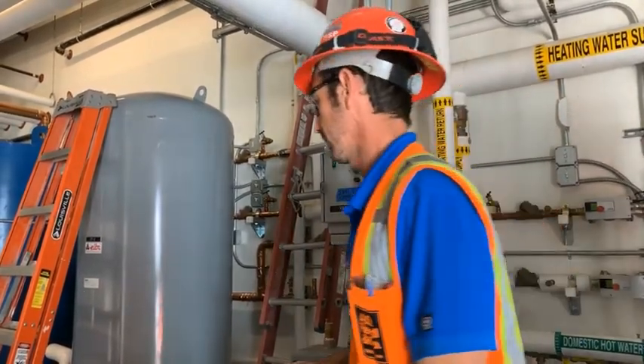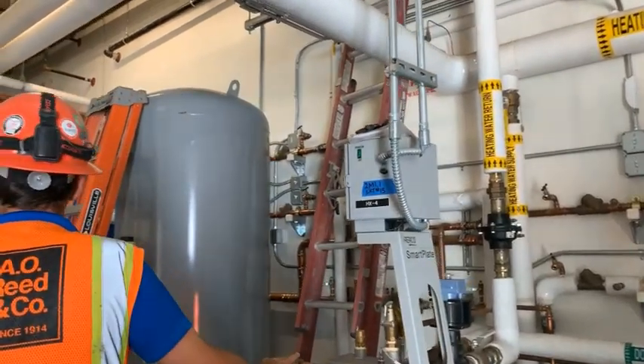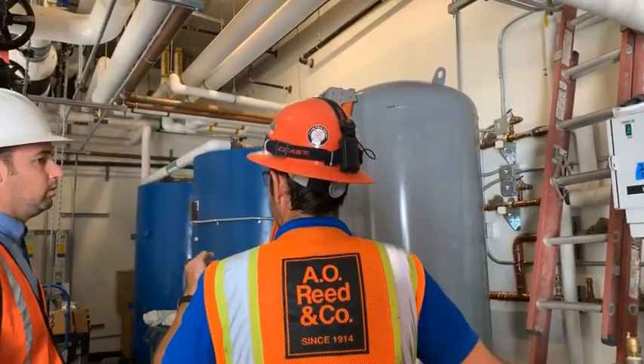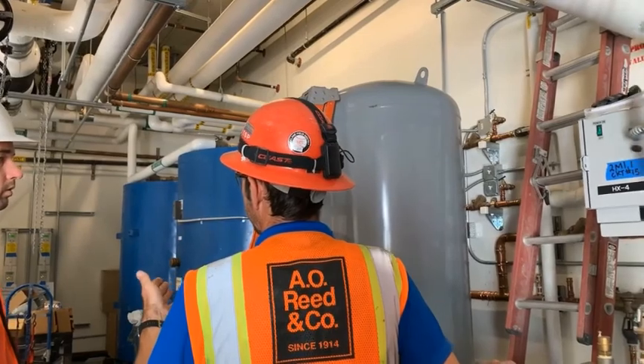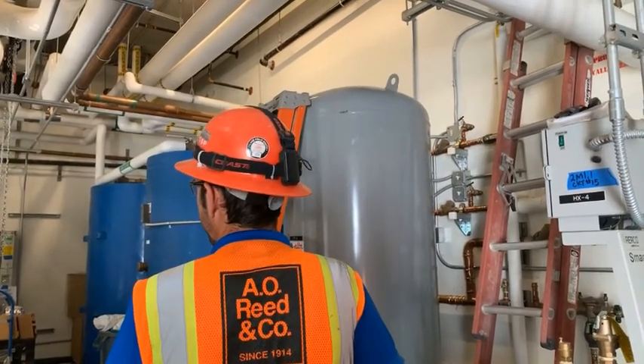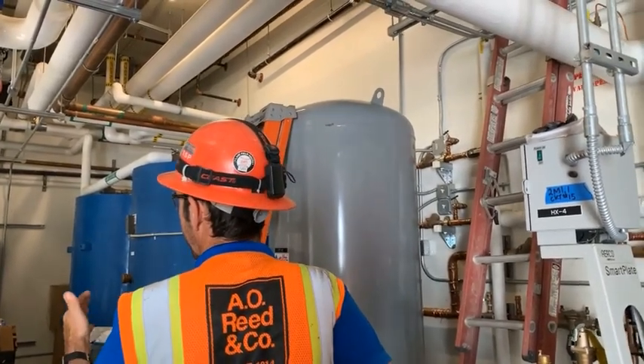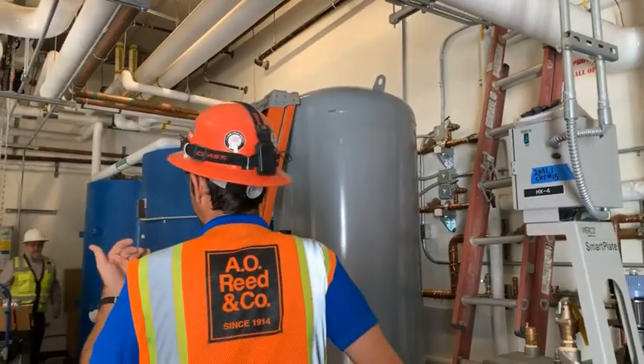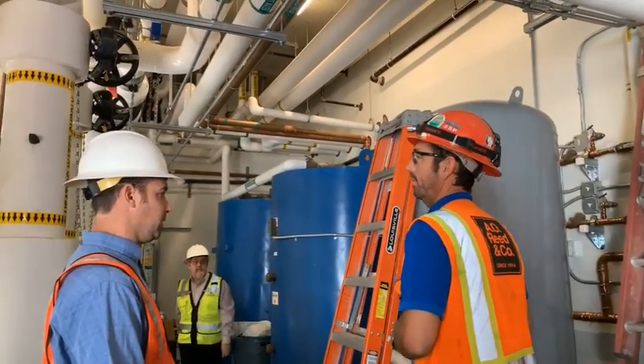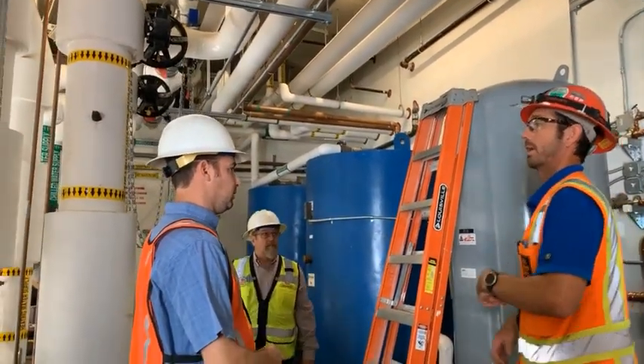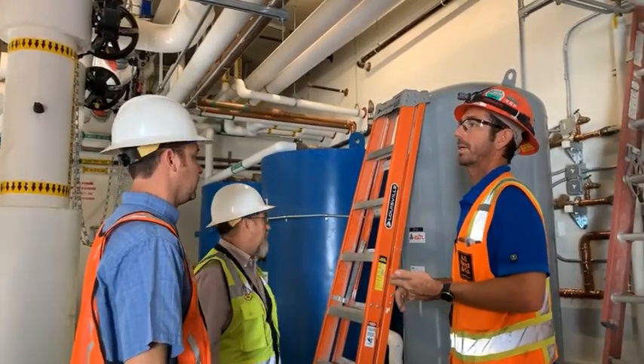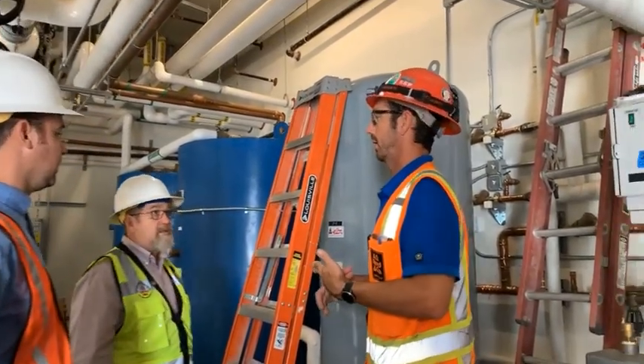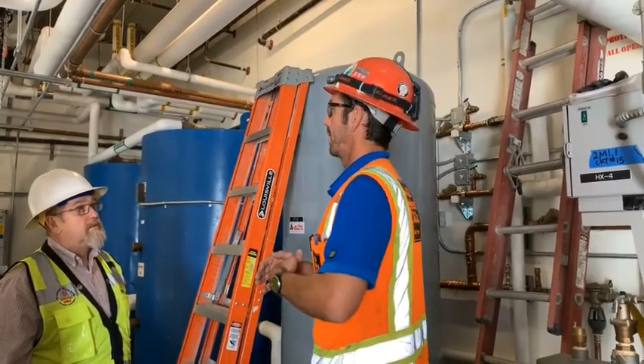That valve does require maintenance. Use the O&M. They have a procedure with how to take it apart and the repair kits you need for gaskets and O-rings to put it back together. On those mixing valves, is the brand that? O&M is owners and maintenance manual, or operation, excuse me. And we're going to get one of those. Yep. You'll get those from Sun. So make sure you follow that.